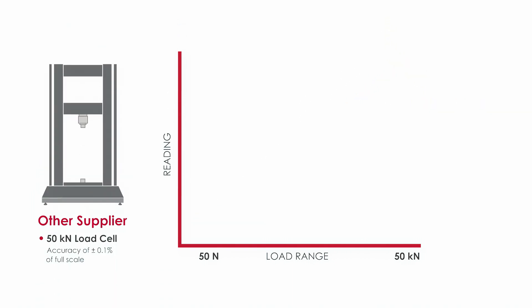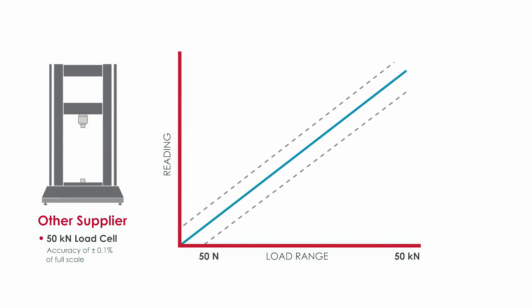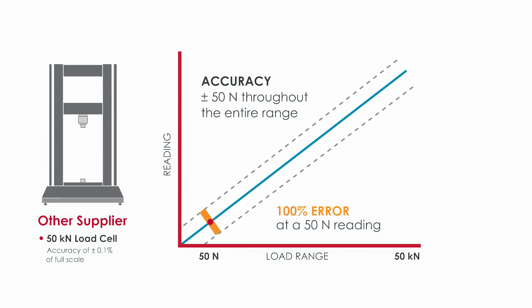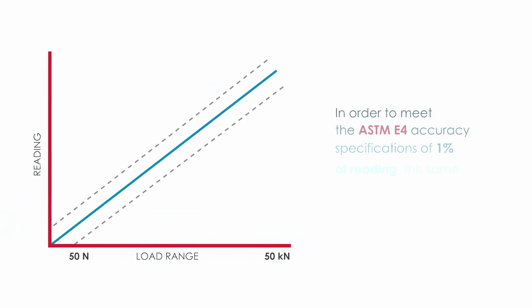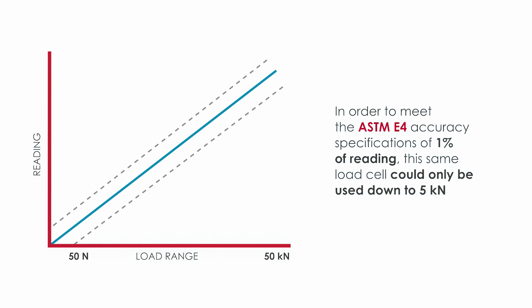Compare that to a similar configuration using a load cell from another supplier that states an accuracy of plus or minus 0.1 percent of the full scale. Remember, in this case the error is constant, so a 50 kilonewton load cell would have an accuracy of plus or minus 50 newtons throughout the entire range. That equates to a 100 percent error at a 50 newton reading. In fact, in order to meet ASTM E4 accuracy specifications of 1 percent of reading, this same load cell could only be used down to 5 kilonewtons.